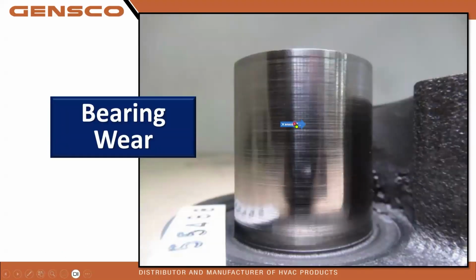This is what bearing wear looks like. Bearing wear on the shaft. See how it's got grooves in it. This was determined by the factory to be caused by silica, sand, some kind of contaminated construction debris. It could be the stuff that comes off your sandpaper that got in the piping, did not get caught, made its way into the compressor, and is now sandblasting and grinding away at the bearing surfaces.